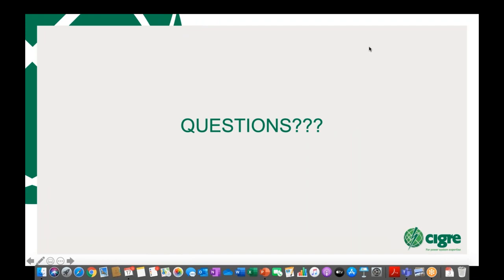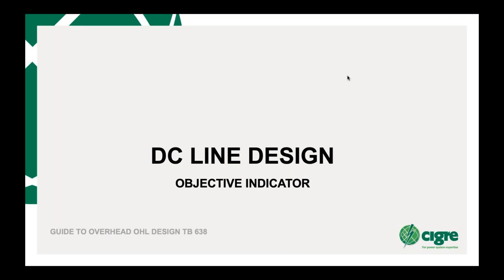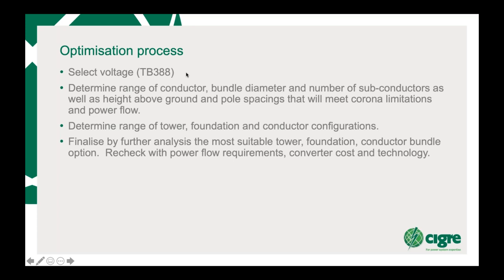We're now just getting on to the objective indicator again for DC line design. So what's the process? Select a voltage, as we said, do we need 600 or 800 here? Determine the range of conductor, bundle diameter, number of subconductors, as well as height above ground and pole spacings that'll meet corona limitations. Determine the range of tower foundation conductor configurations and finalize the most suitable tower foundation bundle option. Then you recheck it with the power flow requirements, converter cost, and technology. Because the big thing, of course, with DC is the converter cost that's in the substations.